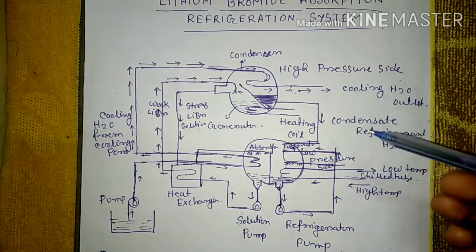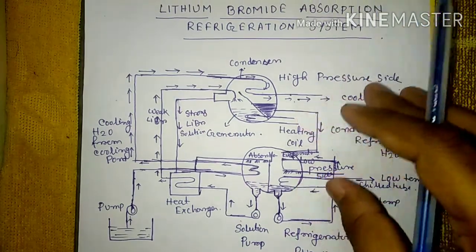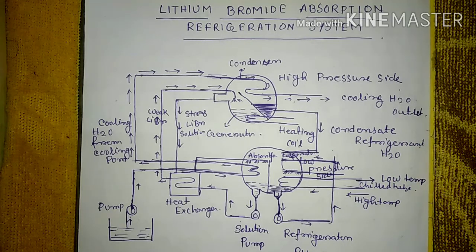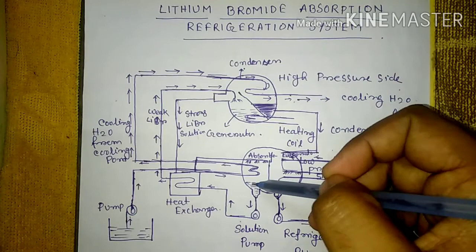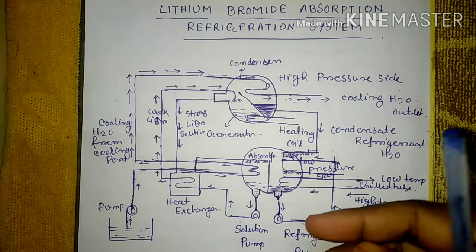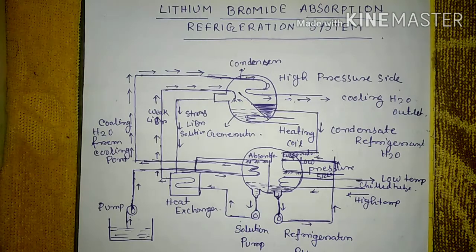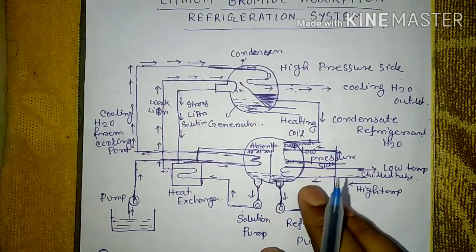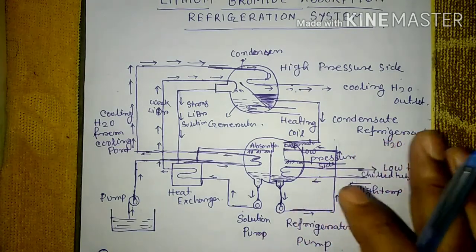One important thing: lithium bromide is corrosive in nature. When it flows through the various metal parts of the system — channels, devices — it can cause corrosive damage. To minimize this corrosion effect on metal parts, lithium bromide inhibitors are generally added.